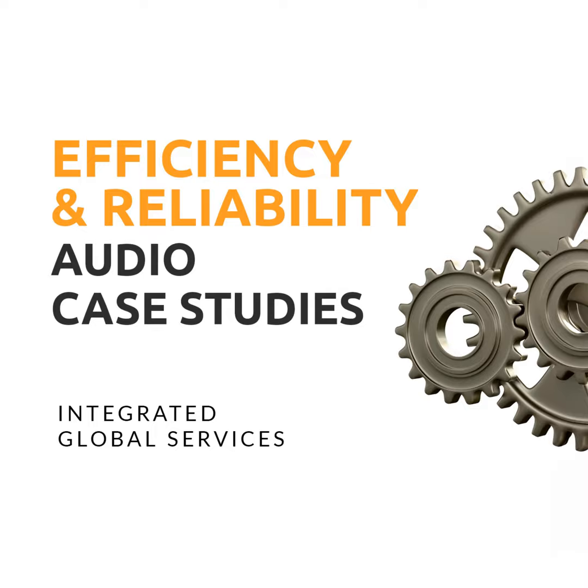This is John, your host, and today's case study explores tackling tube coking and phase separation in vacuum unit heaters to improve operational efficiency and minimize downtime. Let's start. When planning a practical, functional, and cost-effective revamp, treating vacuum unit heater inlet through ejector outlet as a single system is essential.